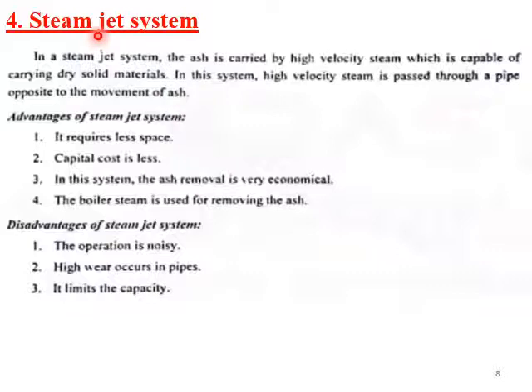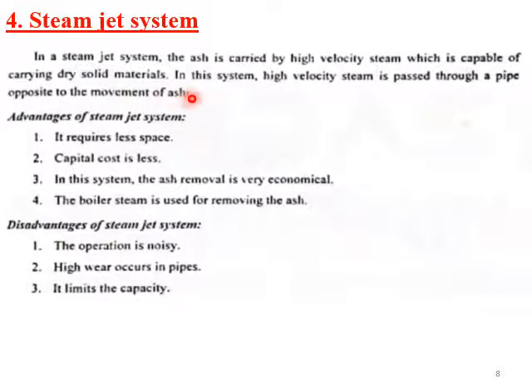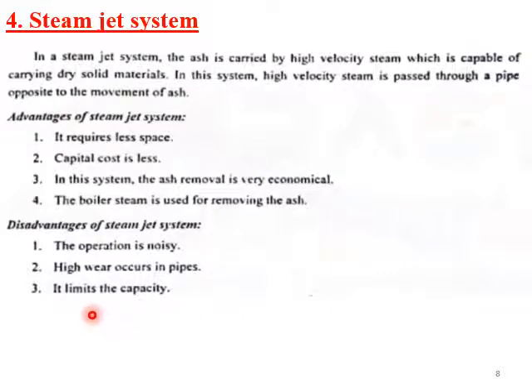The fourth method is the Steam Jet System. Steam is passed at high velocity in the opposite direction to the ash flow. The steam carries the ash to the ash disposal area. So, we have: first, vacuum; second, hydraulic slurry; third, mechanical conveyer; and fourth, steam jet system.